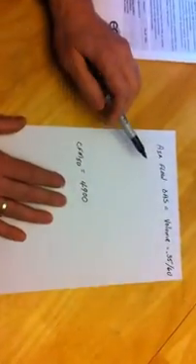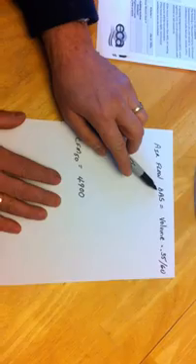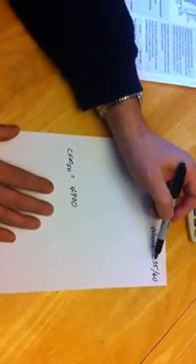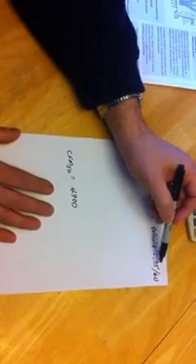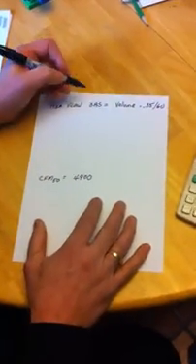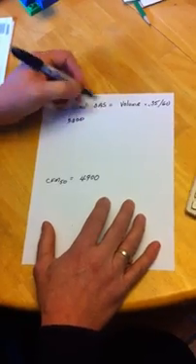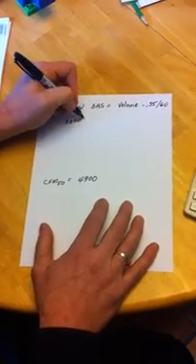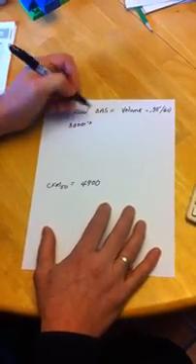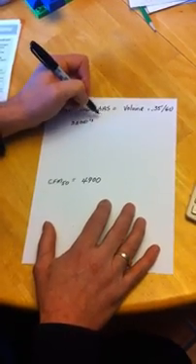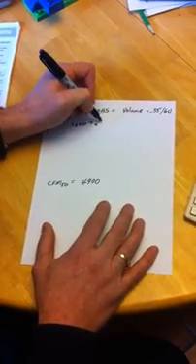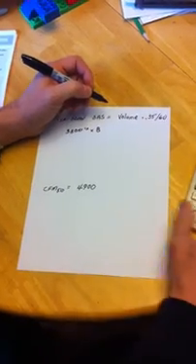Your building air tightness standard is the volume of the building times 0.35. They use 0.35 air changes per hour, and we divide that by 60 minutes every hour to get a CFM. The volume of this house: it's a 3,300 square foot house, so we take 3,300 square feet times 8, the ceiling height, and that gives us the volume.